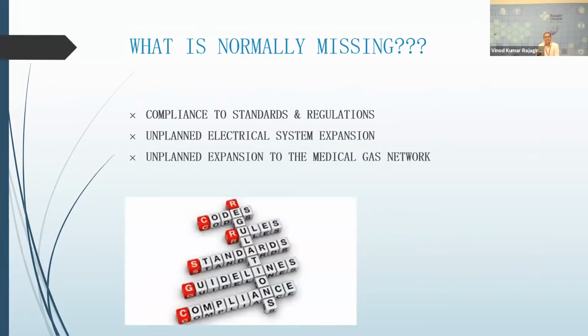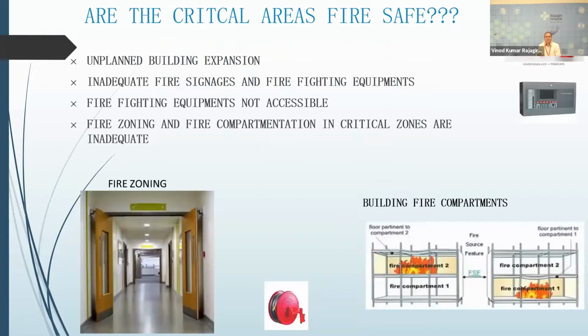Normally, what we see missing is that the buildings don't comply with standards or regulations, and that becomes the first missing link where things could go wrong. Another important issue that we see is the expansion of the electrical system in the areas where there are critical spaces without any planning, and the expansions become a problem. Similar expansions do happen to the medical gas network without any planning, as a result of which you are straining the system, not only the medical gas but also the electrical system, because of the expansion.